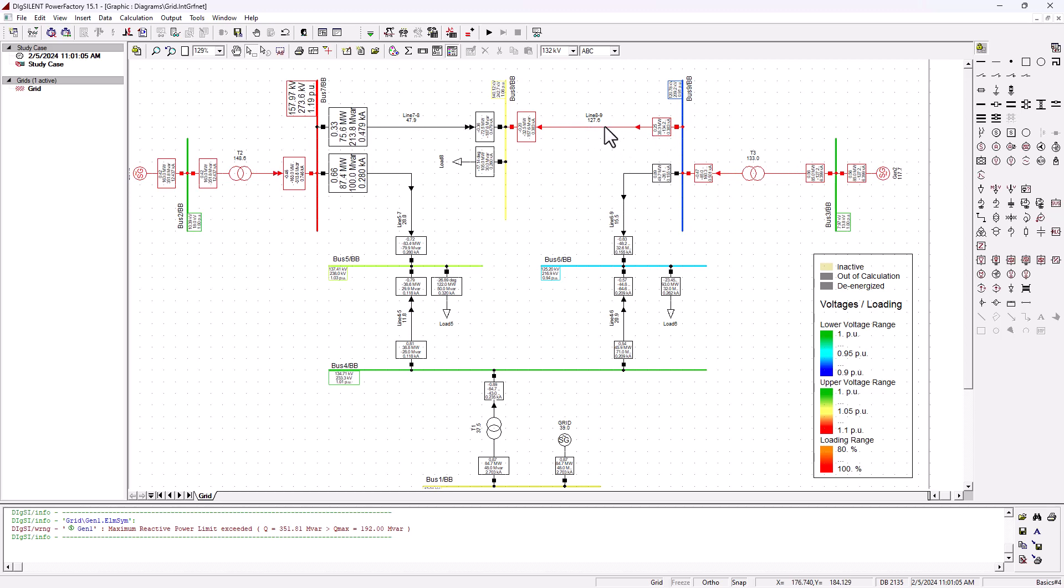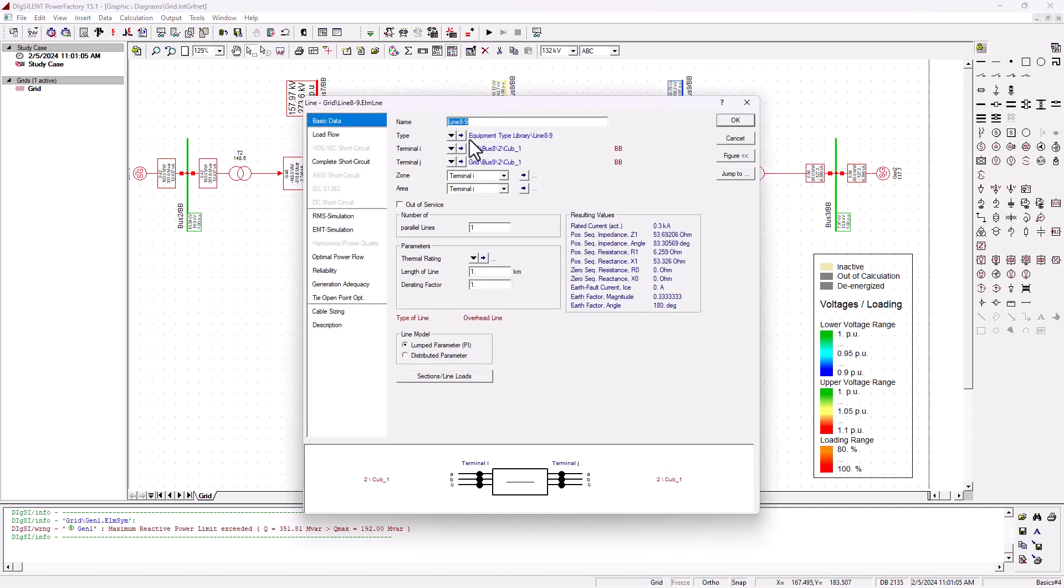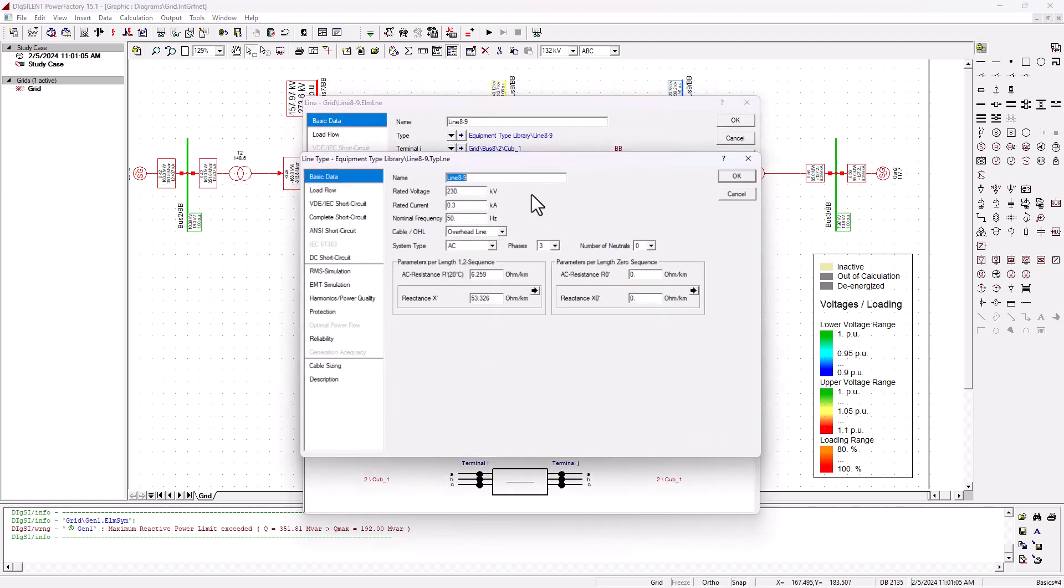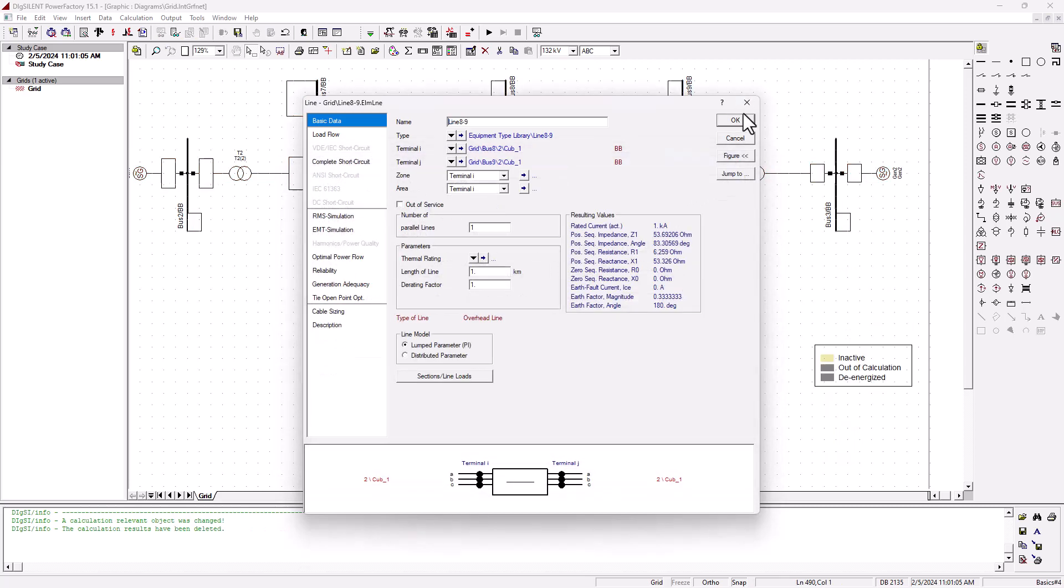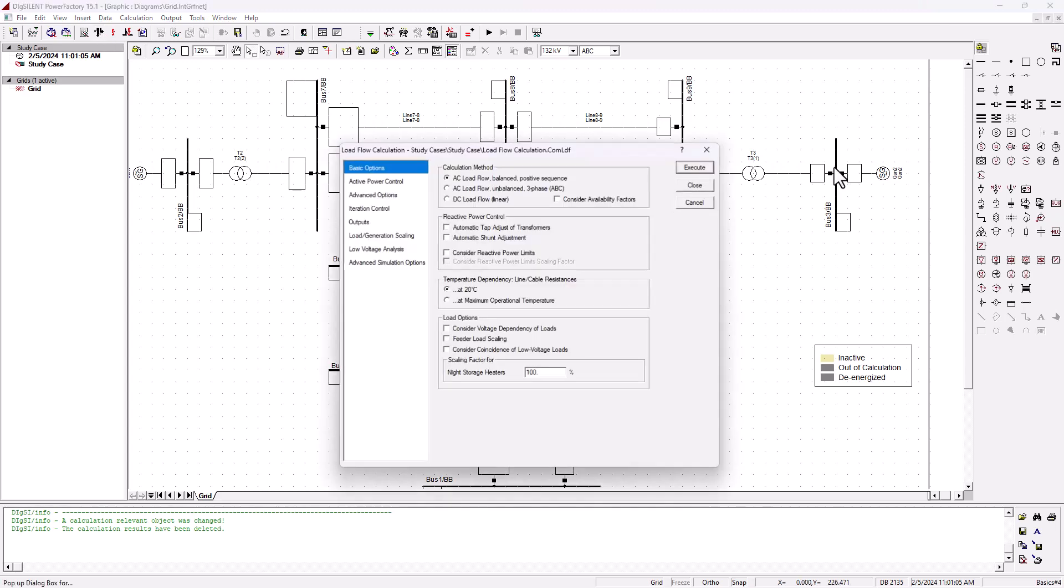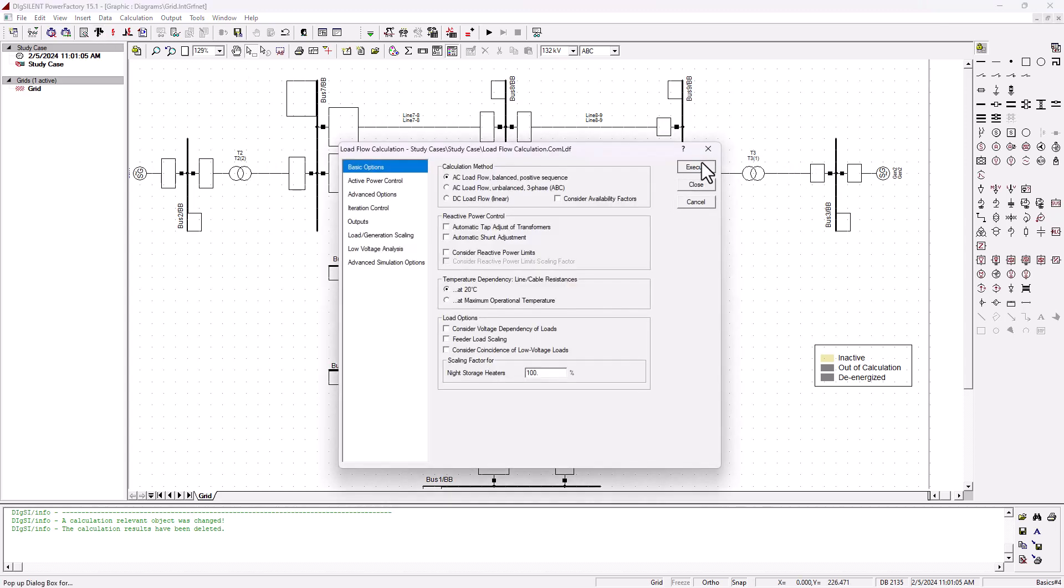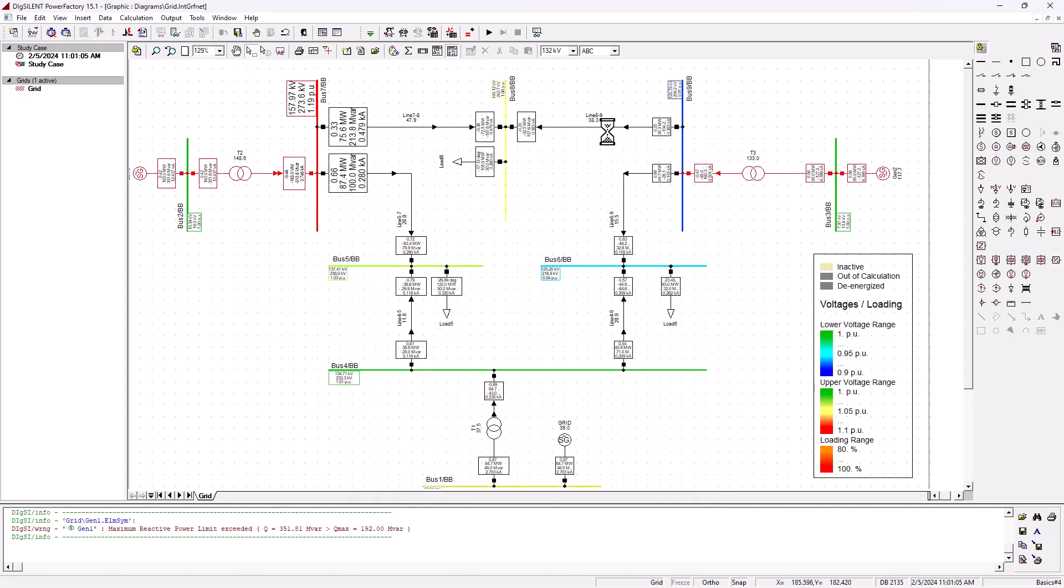Those are problems that must also be addressed. For this one to be addressed, obviously, it's very simple. You have to go back in there and increase your cable ratings. That's going to cost you money and you execute your load flow analysis again. And it is back to normal.